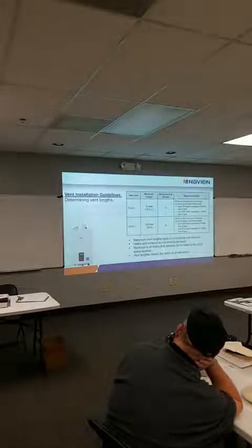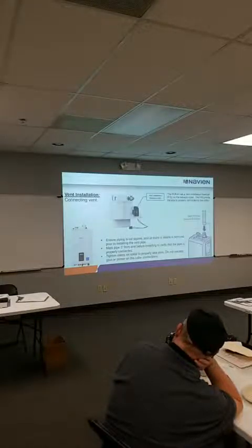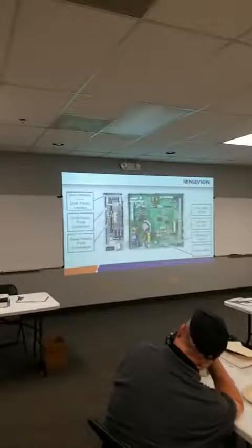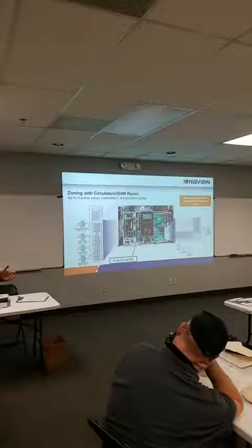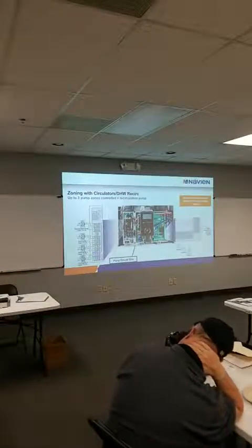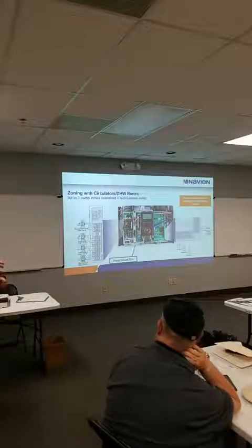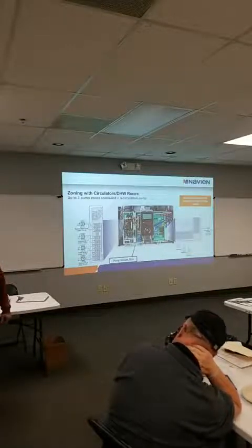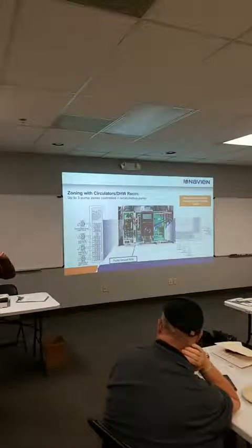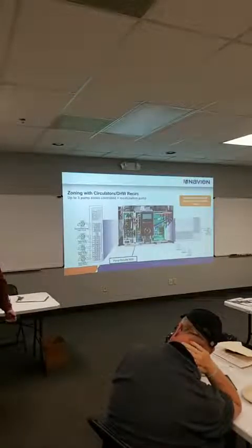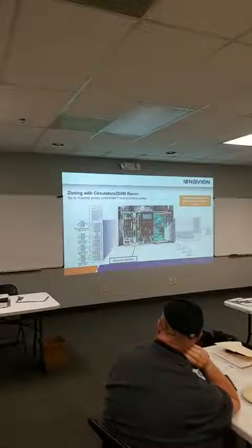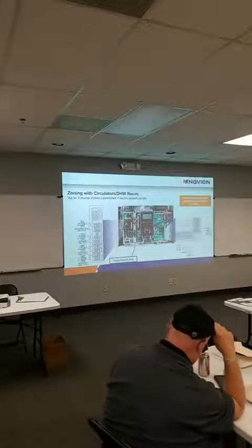LP conversion is the same: dip switches, same venting, and we're out to 65 feet on 2-inch. There's their vent installation detector again. Another key thing on this vent installation detector: when you go to multiple units, the one that comes in the kit does not have the vent installation detector in it, but it comes with a little jumper wire. Where that Molex connector is for the VID, you just unplug it and plug the jumper in, and we're basically bypassing it at that point. On just the lead one? On all of them, because you've got the dampers in there. Correct.